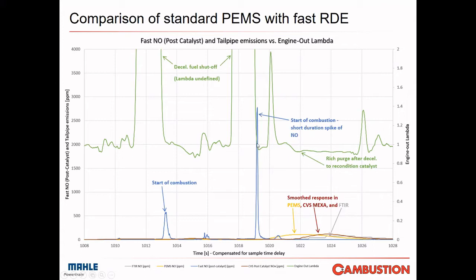And if I were to plot on there the spark timing, the fuel injection timing, the EGR, etc., because they are all already time aligned, you can start to change these parameters and see if you can minimize, bring down this spike of emissions. Now, the other instruments are also measuring that same spike, and they're measuring it accurately, they're capturing it, but because they have a much slower response, maybe 1,000 times slower, this is smoothed out, the peak is not so high, and it's very difficult to identify which of these lambda transients is associated with this hump of emissions which are being recorded by the slower analyzers.